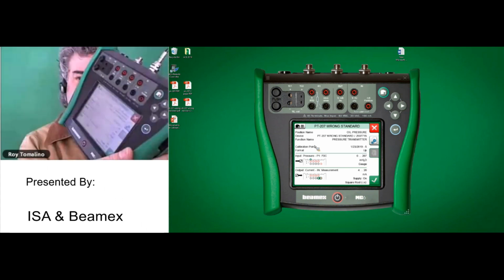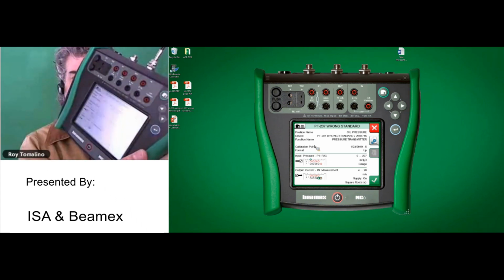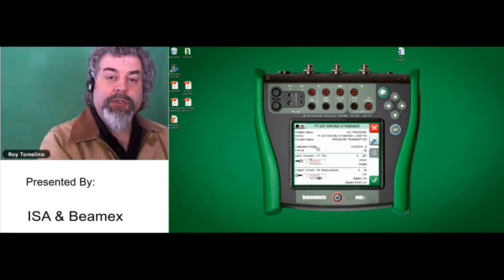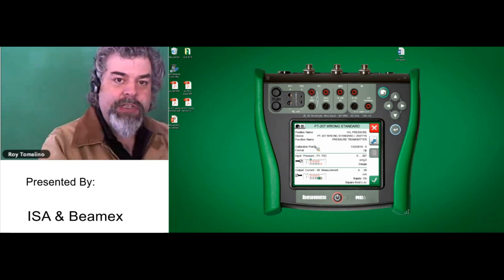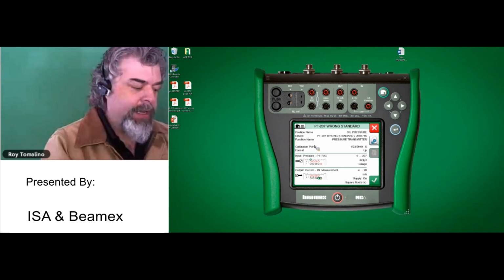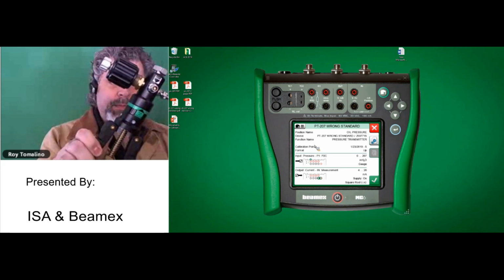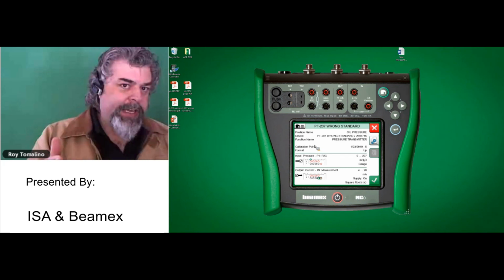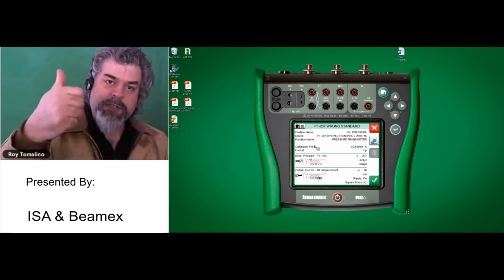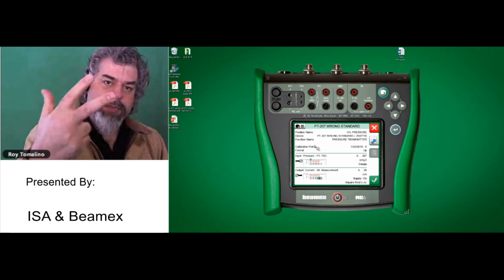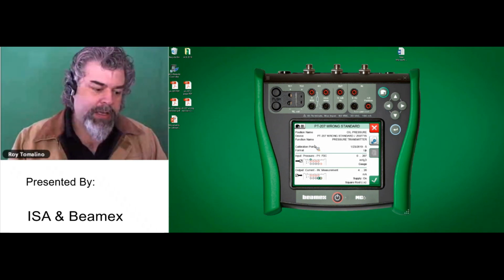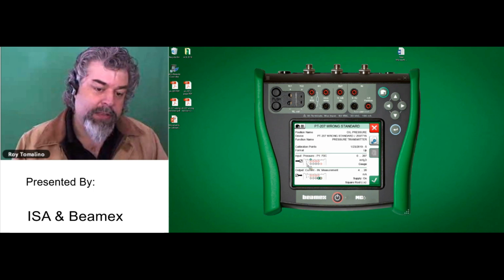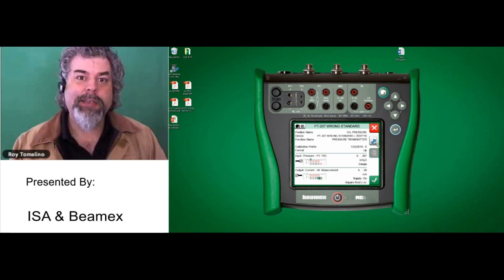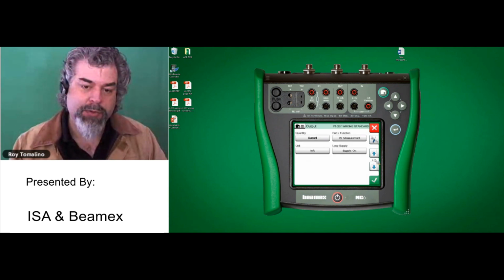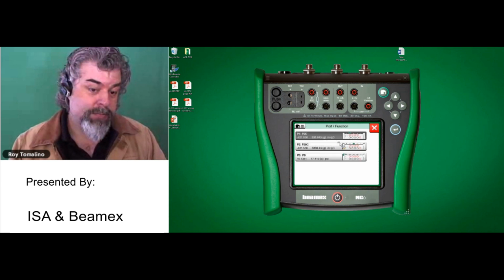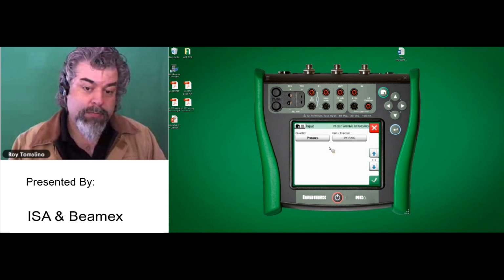I'm running my MC6 calibrator, and you're seeing a live reading on the screen. This is not an emulator. You're seeing exactly what's going on right in front of me. And then I have a pressure pump that I'm using as well. I have a three-legged hose: one goes to my unit under test, the second to the calibrator, and the third to my pressure source. This is showing me where to plug in. I need to be on this pressure module, which, you know what, it did pick the correct pressure module, but I want to pick the wrong one to prove a point.